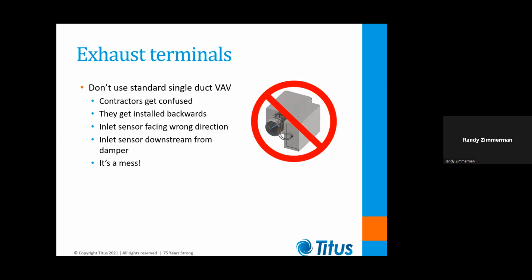install a supply box because they do that all the time. But if you hand them that same box and tell them it's an exhaust box, there's going to be a tendency to go, let's see, exhaust. I need to flip this box around backwards and put the rectangular discharge facing towards the room and the round inlet duct facing the exhaust fan. And that creates problems because that puts the flow sensor on the wrong side of the damper, and it has the flow sensor pointing in the wrong direction.